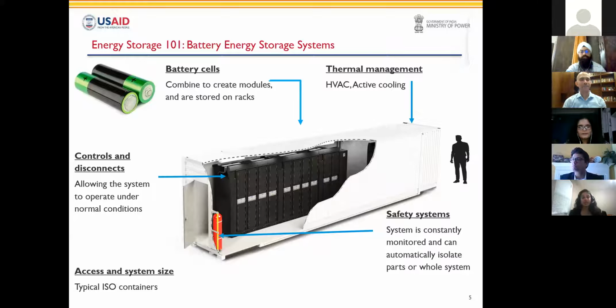Also an important piece here is the thermal management system, both at the module as well as the enclosure level. This provides much needed temperature balancing for the cells, as cells get heated with use, which degrades their performance. This is in the form of air-cooled HVAC systems or liquid-cooled systems, and we'll see shortly why that's a critical piece of the design.